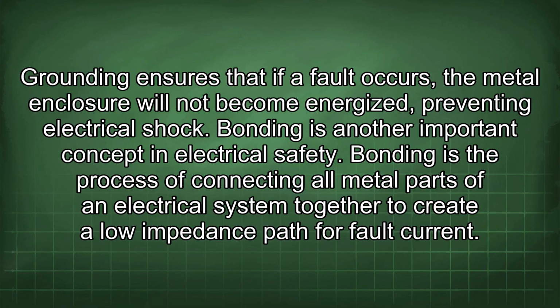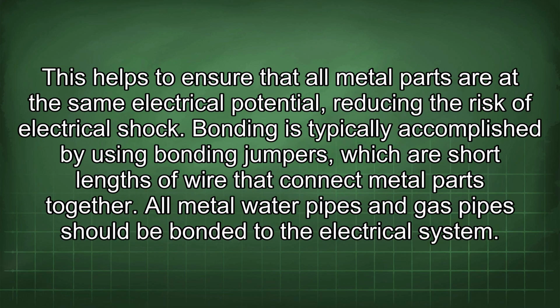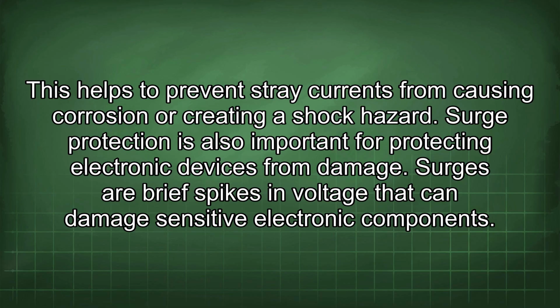Bonding is another important concept in electrical safety. Bonding is the process of connecting all metal parts of an electrical system together to create a low impedance path for fault current. This helps to ensure that all metal parts are at the same electrical potential, reducing the risk of electrical shock. Bonding is typically accomplished by using bonding jumpers, which are short lengths of wire that connect metal parts together. All metal water pipes and gas pipes should be bonded to the electrical system. This helps to prevent stray currents from causing corrosion or creating a shock hazard. Surge protection is also important for protecting electronic devices from damage. Surges are brief spikes in voltage that can damage sensitive electronic components.